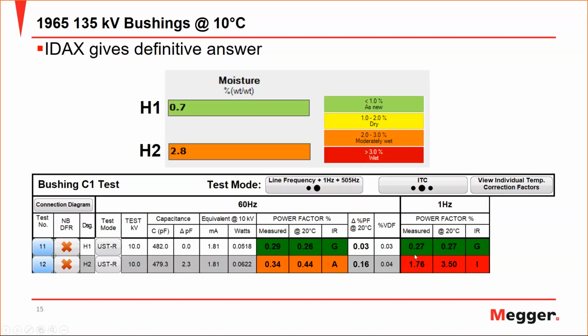I would assume that if there's an electrical stress, and perhaps Diego can comment on this, if there was an electrical stress that did not change the moisture or the oil conductivity, I would expect the capacitance to change. And I don't think that 1 hertz would provide any additional information. I think the capacitance might be enough there. Would you agree with that, Diego?